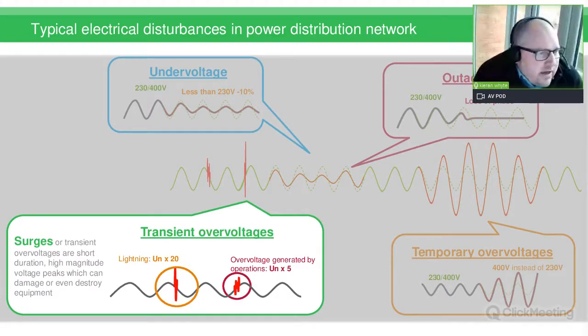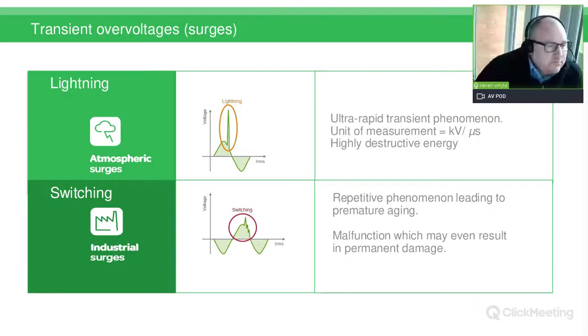Typical electrical disturbances in a power distribution network. Surges or transient overvoltages are short duration, high magnitude voltage peaks, which can damage or even destroy equipment. So we're looking at high magnitude for a short duration, and it's this peak which causes the damage to the appliances.